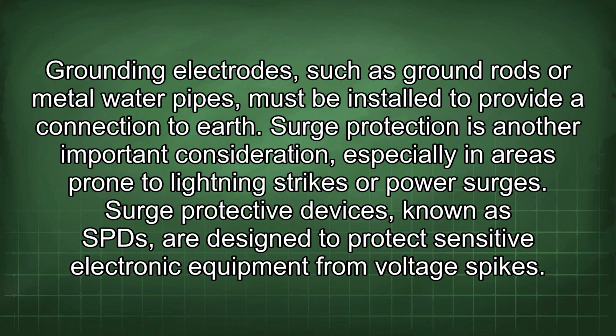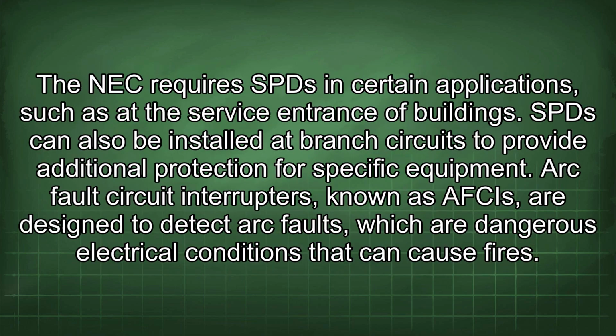Surge protection is another important consideration, especially in areas prone to lightning strikes or power surges. Surge protective devices, known as SPD, are designed to protect sensitive electronic equipment from voltage spikes. The NEC requires SPD in certain applications, such as at the service entrance of buildings. SPD can also be installed at branch circuits to provide additional protection for specific equipment.